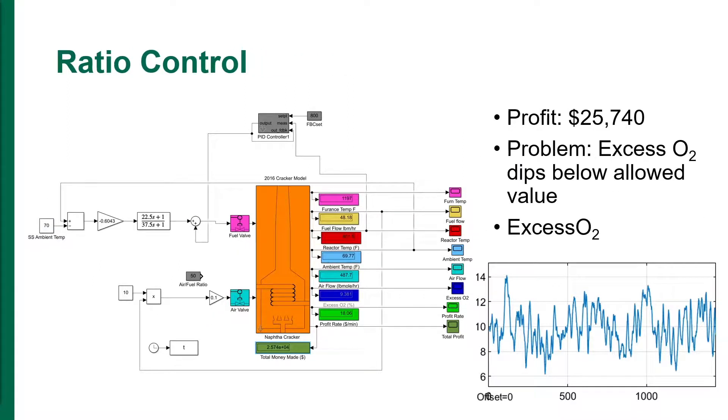In order to control the excess O2 at the set point, a ratio controller between the fuel flow and the air flow was implemented. The ratio of the air flow to the fuel flow is 10. The resulting profit was $25,740. However, the excess O2 crossed the minimum allowable value multiple times, which resulted in safety issues. Thus, the next objective is to control the excess O2.